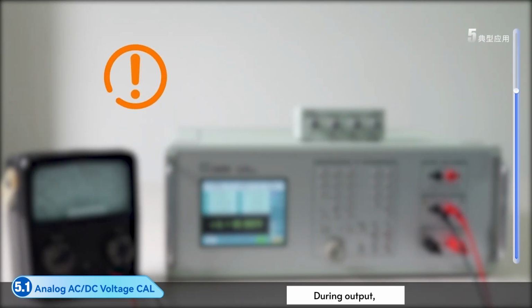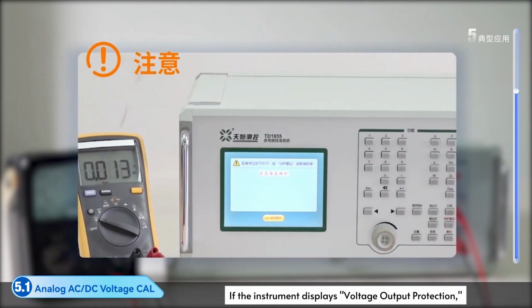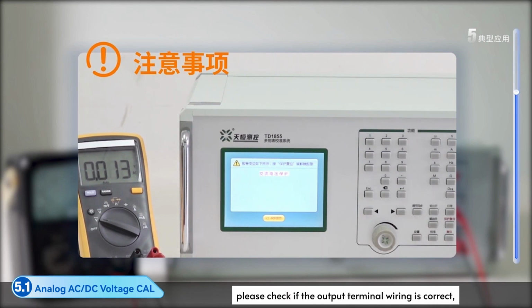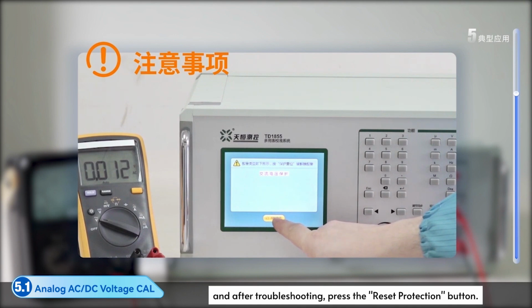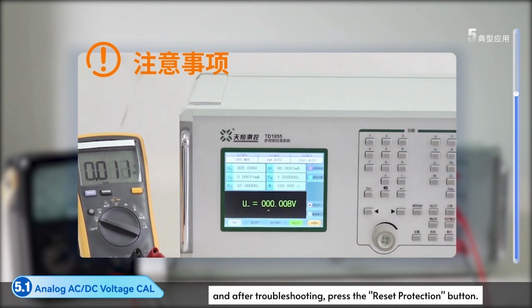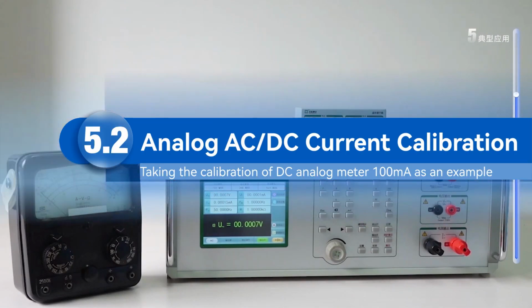During output, if the instrument displays voltage output protection, please check if the output terminal wiring is correct. Check if the load is too large or damaged. And after troubleshooting, press the Reset Protection button. Part 2. Analog AC/DC Current Calibration.